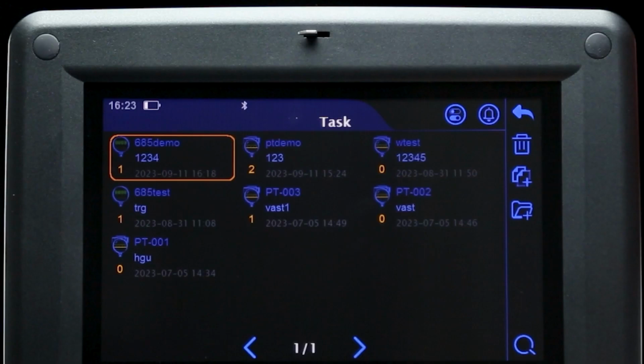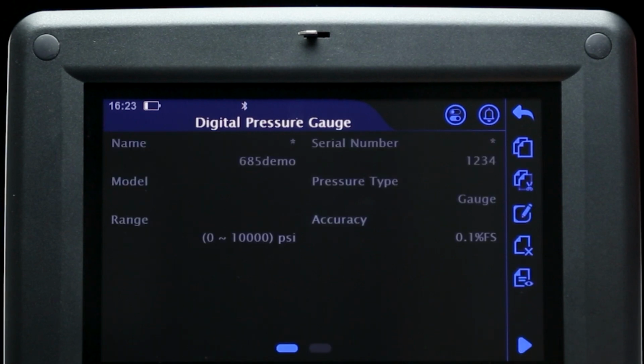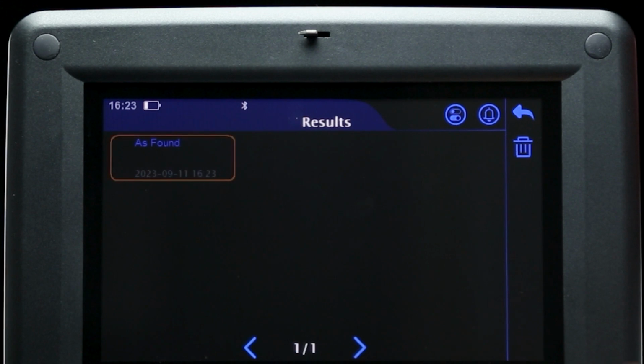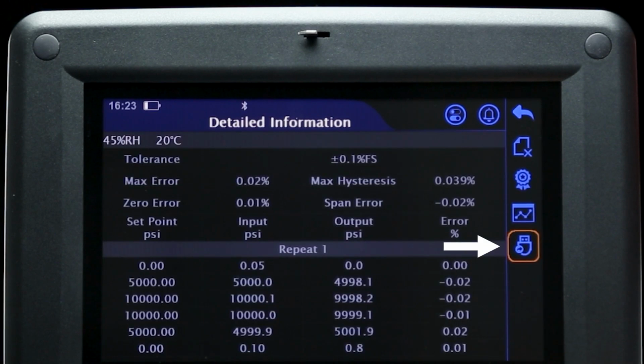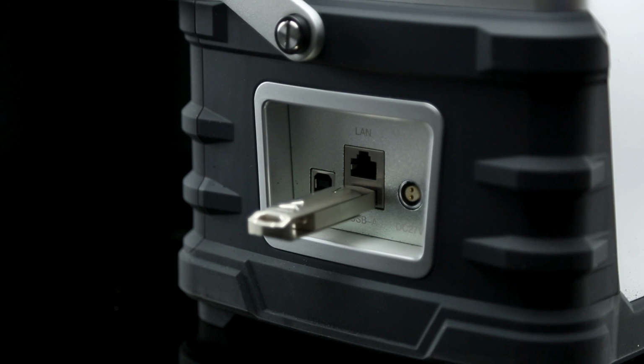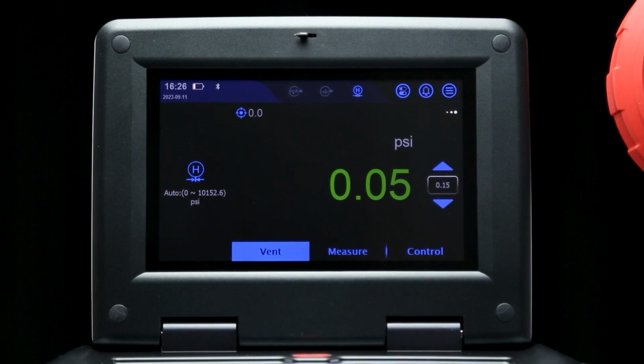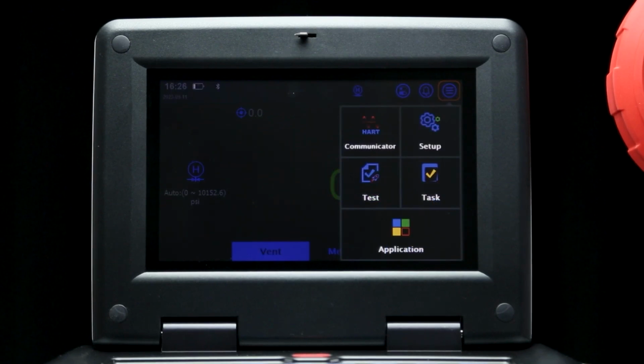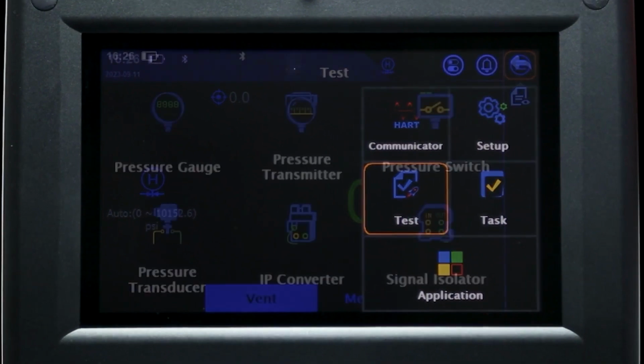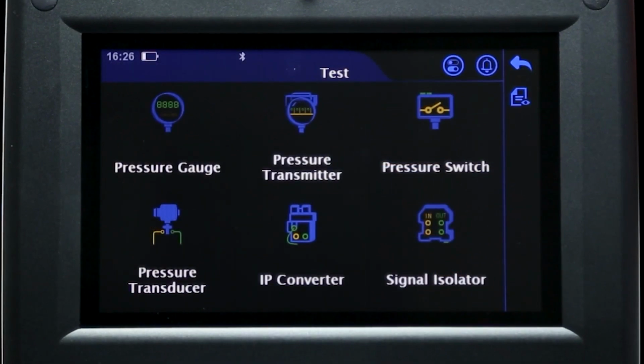Test data can now be exported or recalled by once again selecting the same device in the task library, then pressing the Previous Test button to view the device records. Select a test and then press the export icon to push the data into an inserted USB drive. If you wish to do a one-time test without saving the device in the task library, you can use the test function and then follow the same prompts as you would in the task function.